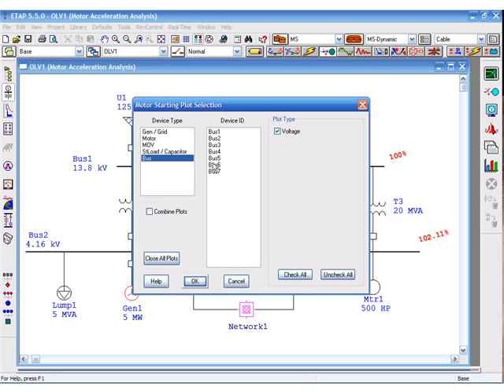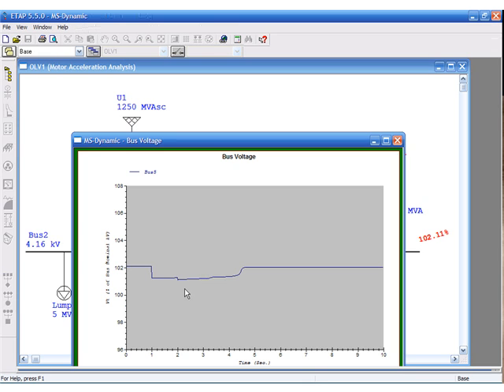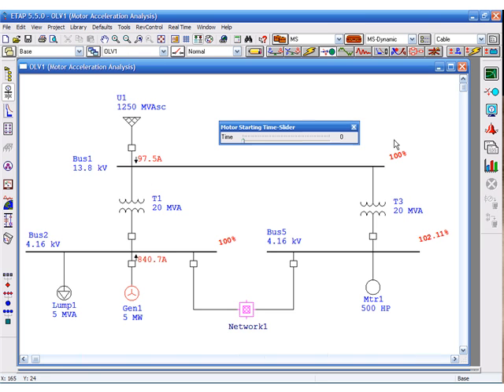If we see the plot for bus 5, we can now see that motor 1 starts off at 1 second. At t equals 2 seconds, there's a further dip indicating the start of another motor that impacts the same bus.